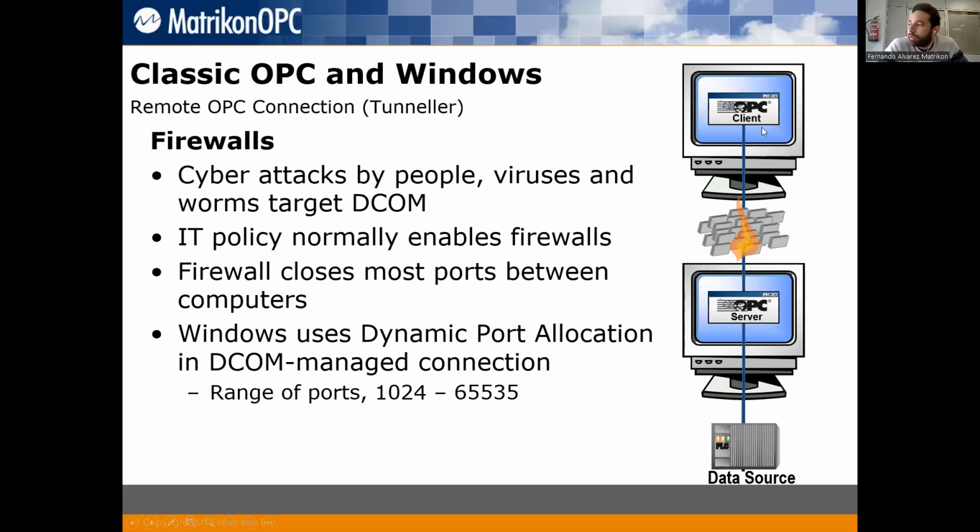I only did a reboot of the computer and it was working before. All right, so we asked them, do you have firewalls in the middle? Yeah, I have firewalls, but before it was working. Well, probably the port was open. That port was open in that moment, but then when you rebooted the computer where the OPC client is, he will select another port, and there is no way to know which port it is. So then probably he tried to connect to the OPC server computer, and that port was blocked in the firewall.